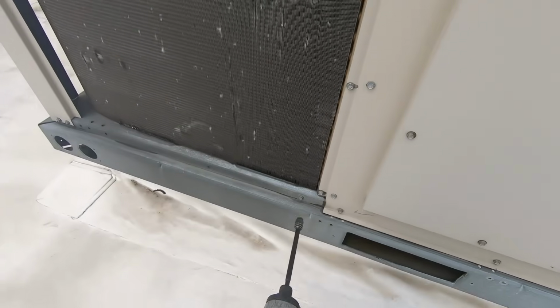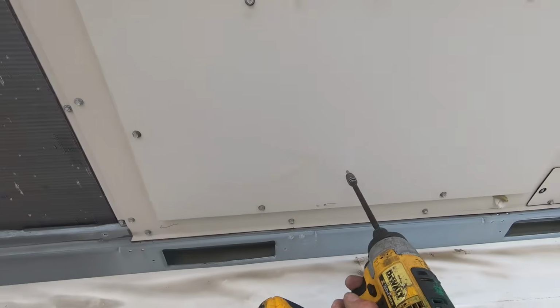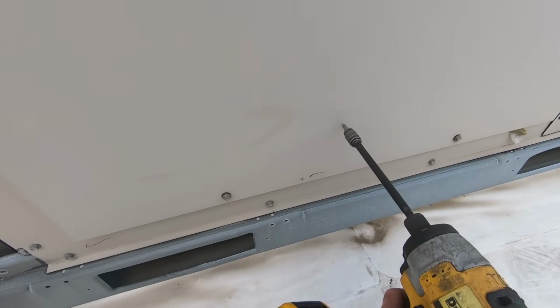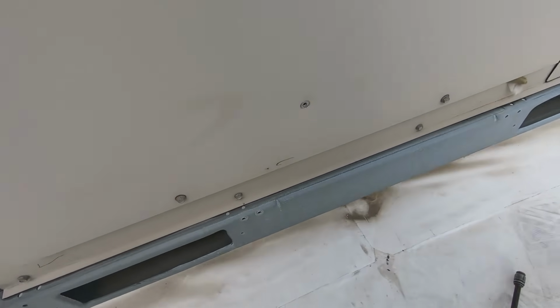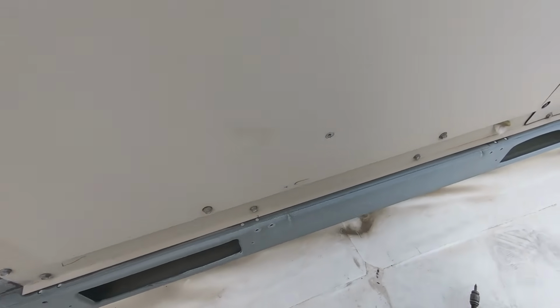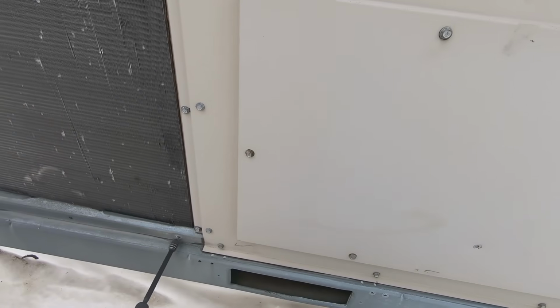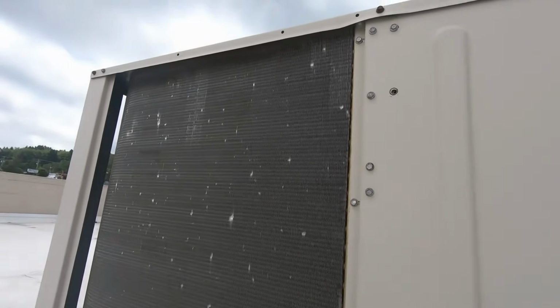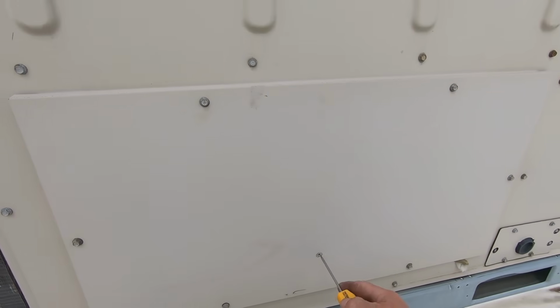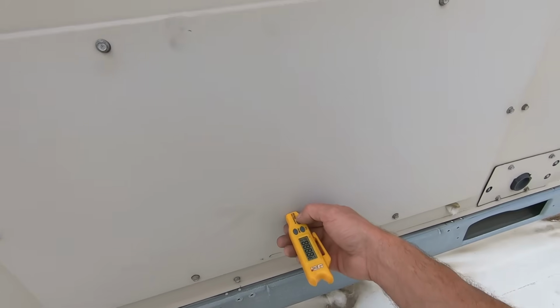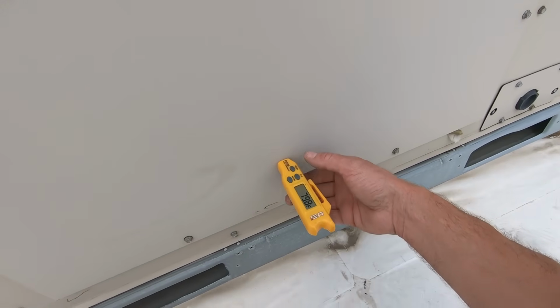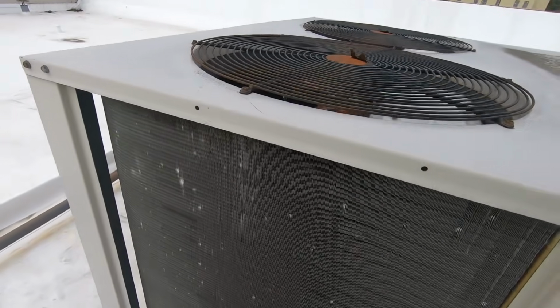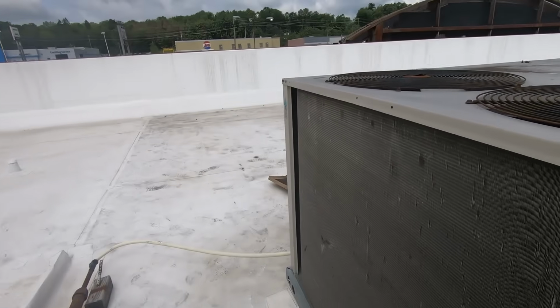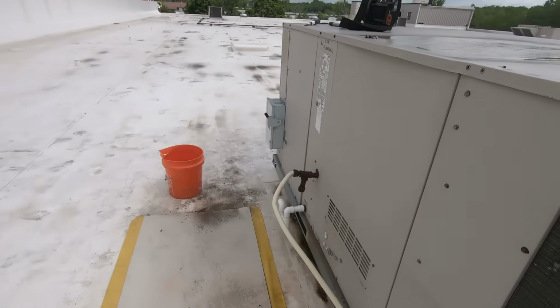Get a supply temp and see what's going on. These coils are going to get cleaned. Part of the write-up, because come on, I don't believe anything's been done here in quite a while, so we're just going to come and start from scratch. Clean these coils. Look how packed. They're dirty up there. I'm going to get a picture of that. They all need chemically cleaned. They all need drain pans cleaned, belts, filters. Make sure they're running and cooling as well as they can right now, but that's what I'm going to do. Write all of that stuff up as usual. You guys know the routine by now.